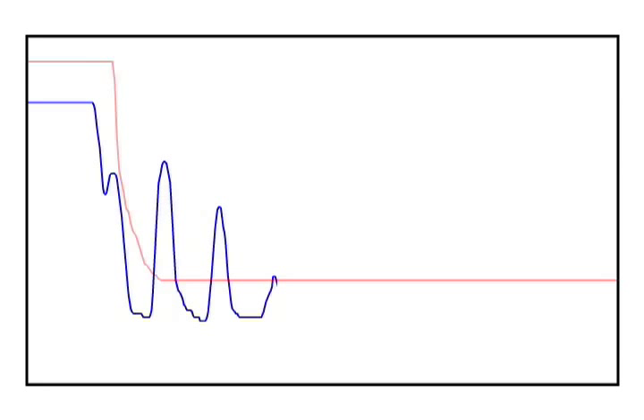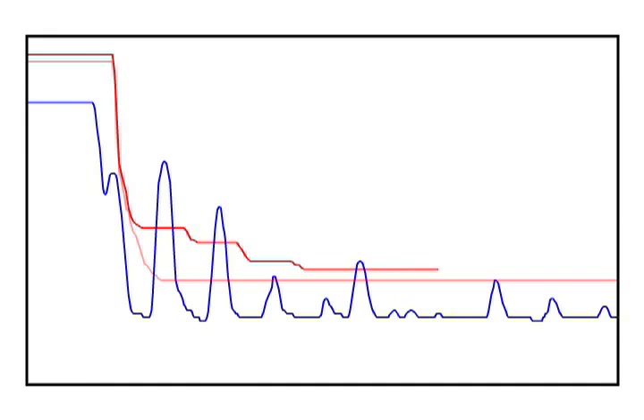Finally, we have an echo that is quite close to the roof of the vessel. We have many multiple echoes. The dynamic TVT adapts to the changes in the vessel. If our TVT curve was not dynamic, we would run the risk of having one of the multiple echoes selected as the true echo.